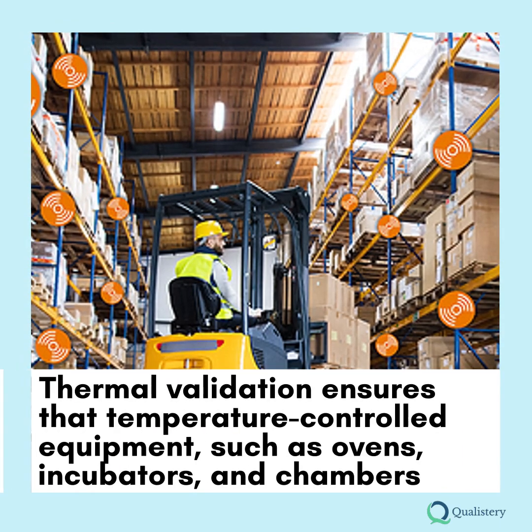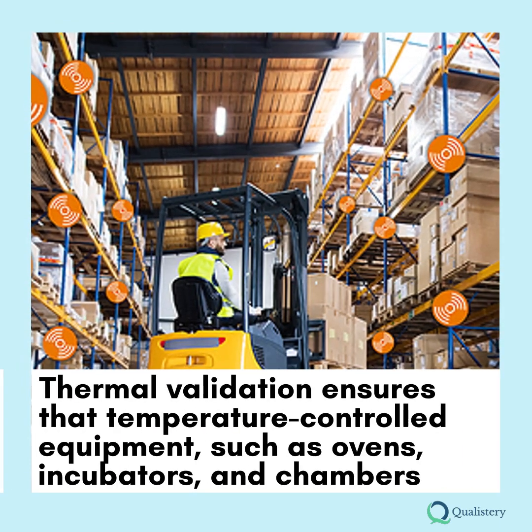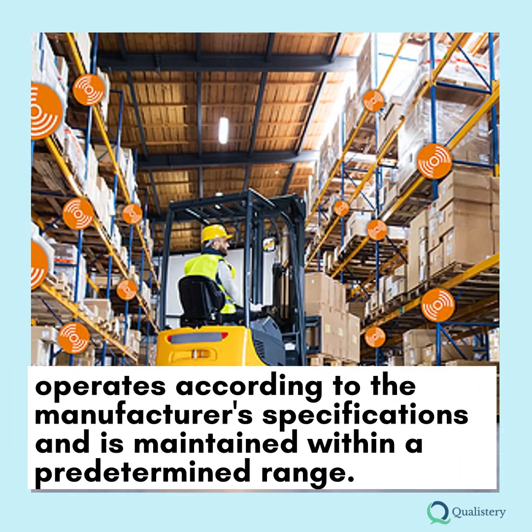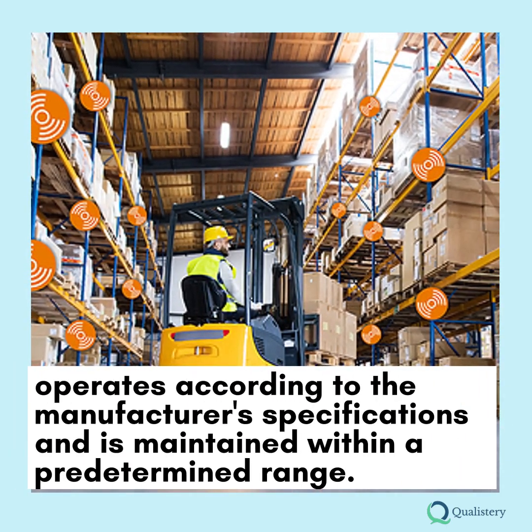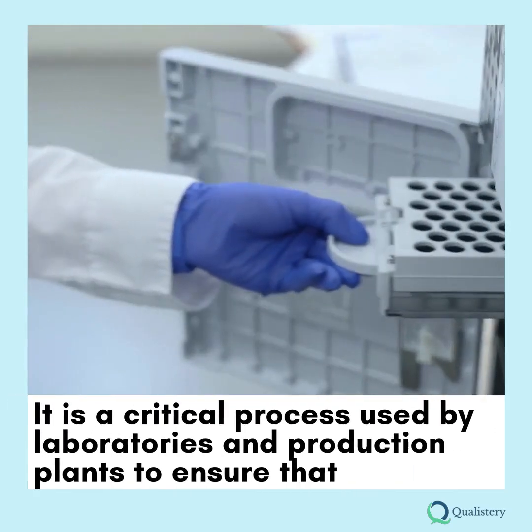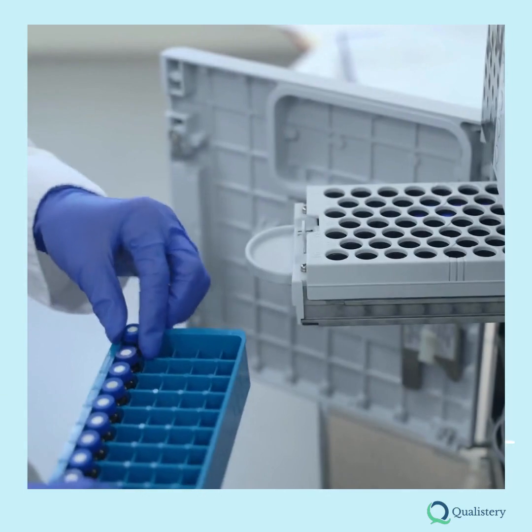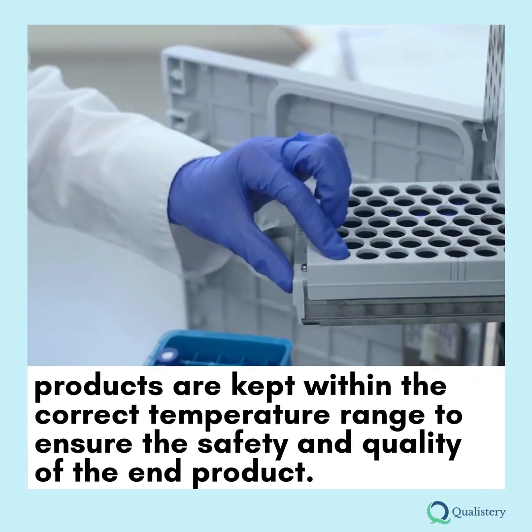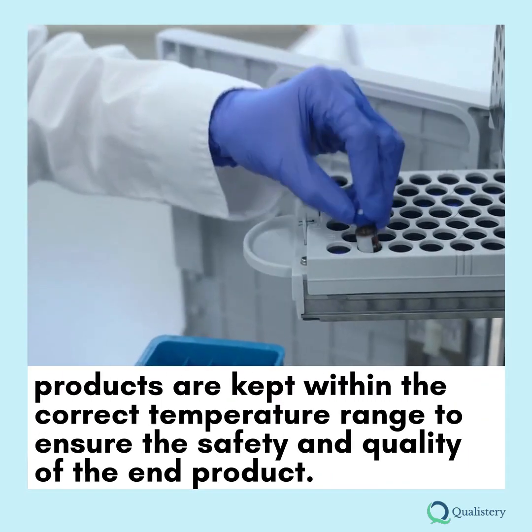Thermal validation ensures that temperature-controlled equipment, such as ovens, incubators, and chambers, operates according to the manufacturer's specifications and is maintained within a predetermined range. It is a critical process used by laboratories and production plants to ensure that products are kept within the correct temperature range to ensure the safety and quality of the end product.